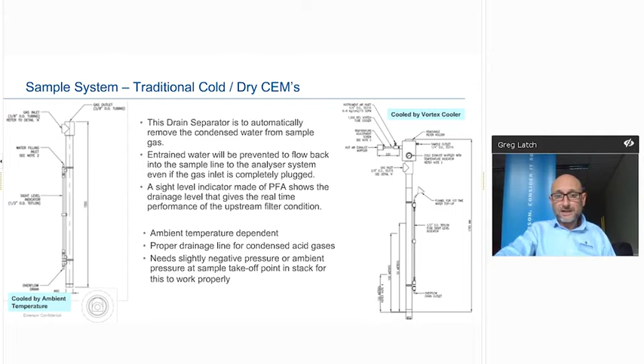Hot wet, this is a little bit of a brief overview, and hopefully it looks fairly clear again coming through as we're moving through the slide deck. Hot wet is a traditional SEMS aspect as well. In this particular case, what we're doing is having the sample handling system and the analysis down typically away from the stack and the high temperatures, and also the hazardous areas from our H&S point of view, general maintenance and the likes. So we're having a heated elevated sample probe, takeoff point, elevated sample transport, and obviously removing all the particulates ideally at the point of takeoff. Obviously then we'd go back and have calibration injection at that point as well of the stack.